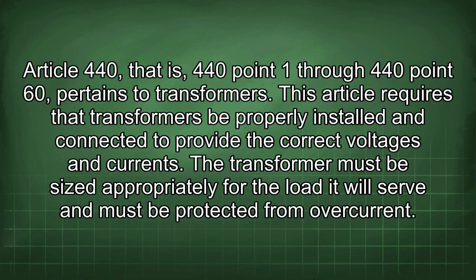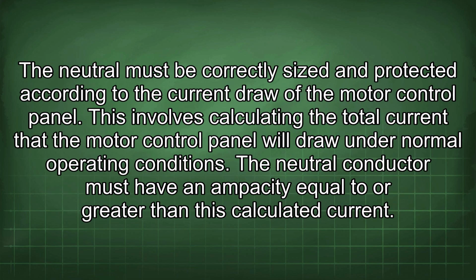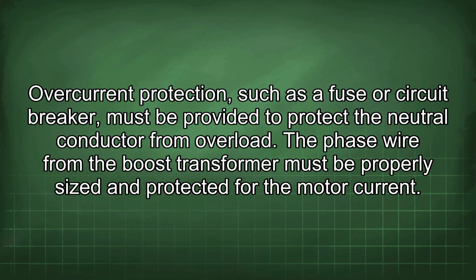The transformer must be sized appropriately for the load it will serve and must be protected from overcurrent. The neutral must be correctly sized and protected according to the current draw of the motor control panel. This involves calculating the total current the motor control panel will draw under normal operating conditions. The neutral conductor must have an ampacity equal to or greater than this calculated current. Overcurrent protection, such as a fuse or circuit breaker, must be provided to protect the neutral conductor from overload.